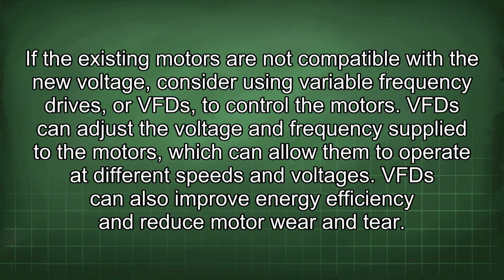If the existing motors are not compatible with the new voltage, consider using variable frequency drives, or VFDs, to control the motors. VFD can adjust the voltage and frequency supplied to the motors, which can allow them to operate at different speeds and voltages. VFD can also improve energy efficiency and reduce motor wear and tear.